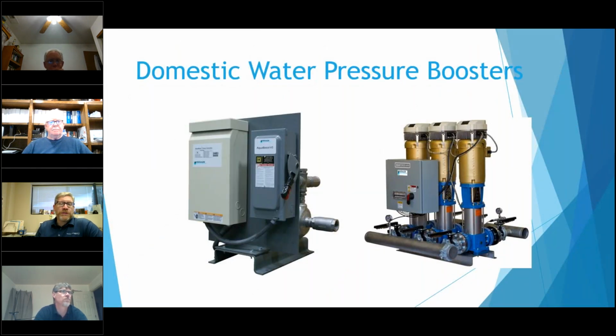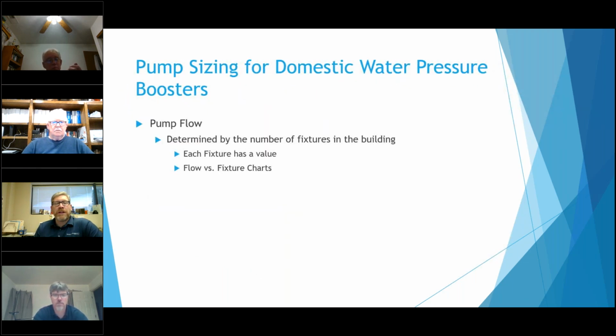Domestic water pressure boosters seem to be quite prevalent lately. Last several years, as people get further and further away from water towers, or when developments get larger and larger, and everyone seems to need more and more pressure. It also doesn't help that a lot of these low flow fixtures require like 40 pounds for them. Like I've heard some flush valves just require 40 pounds just to work. So a lot of places are needing some type of pressure booster.